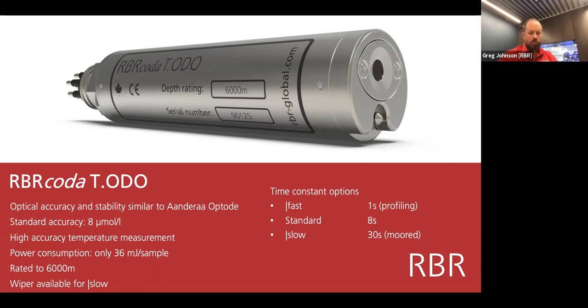One of the fundamental things that drove our development here was indeed the power consumption, and making sure that when you have a CTD that only consumes a fraction of the power of electrode-based CTDs, if you added an Aanderaa optode, you'd wonder why you bothered making the CTD so efficient, because its power efficiency was demolished as a system by the optical sensor. However, with our own optode being only 25% of the power consumption, we now have the ability to make complete instruments with CTD and oxygen in long-lived packages.